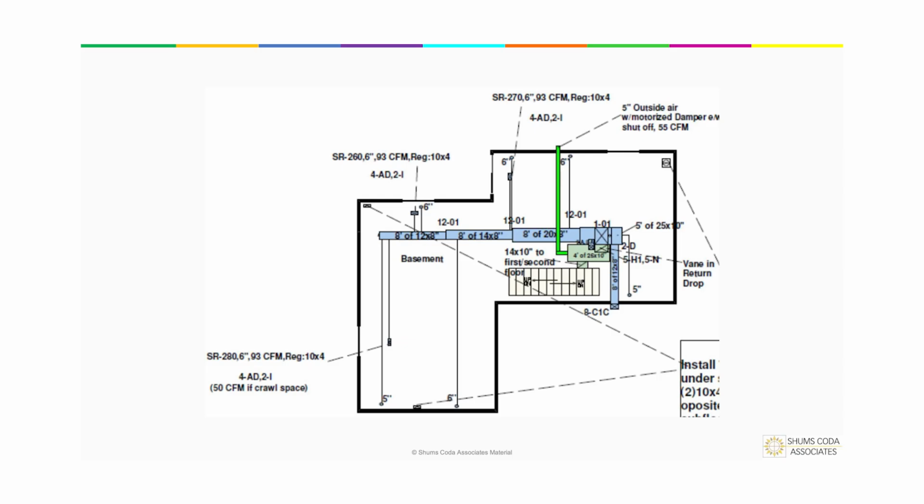Now here's another example. I think this one is Wrightsoft. This one is an Elite, I want to say. So it doesn't quite give us as much information, but I do know that this is 5 inches. We got 5 inches here. This is just the trunk line. Well, it doesn't have all that information, but here's another example of a Manual D we might get.